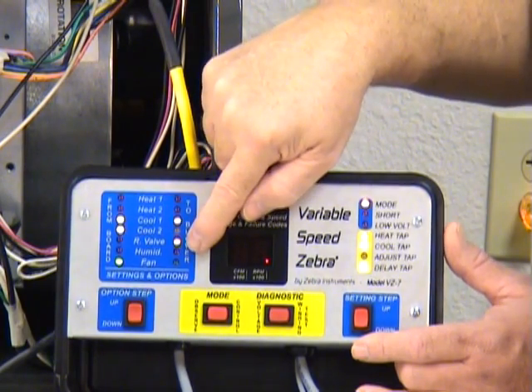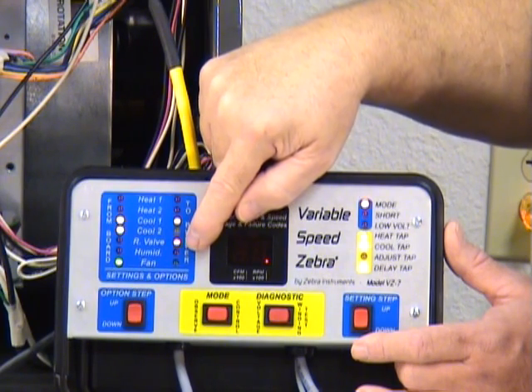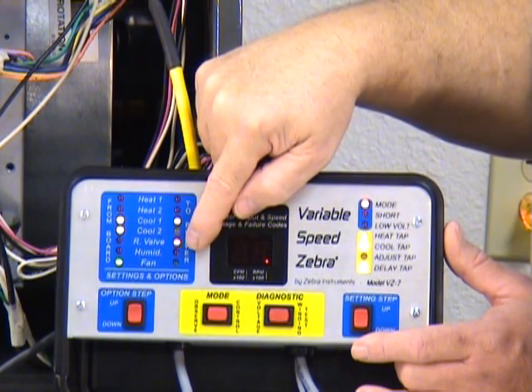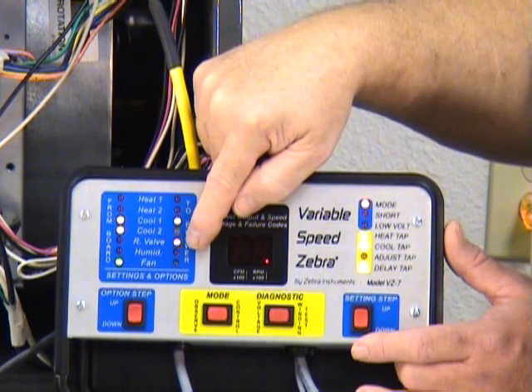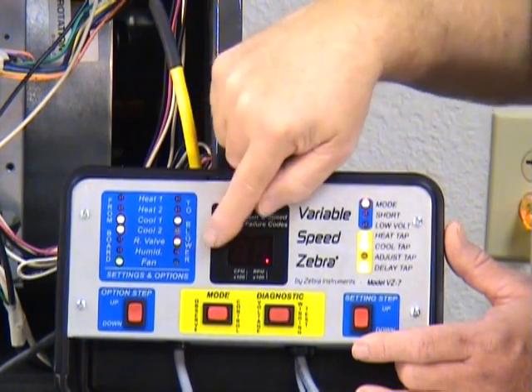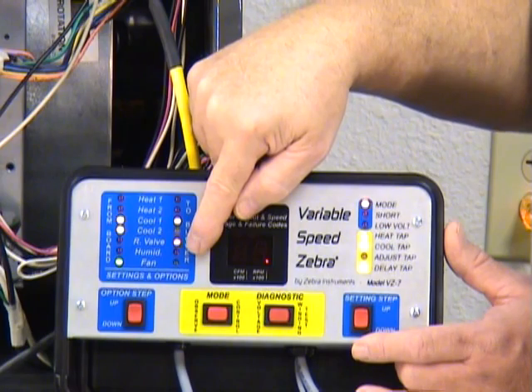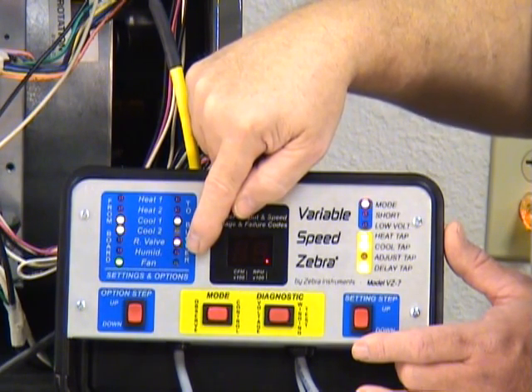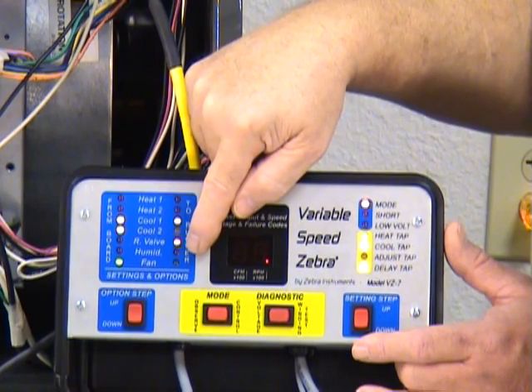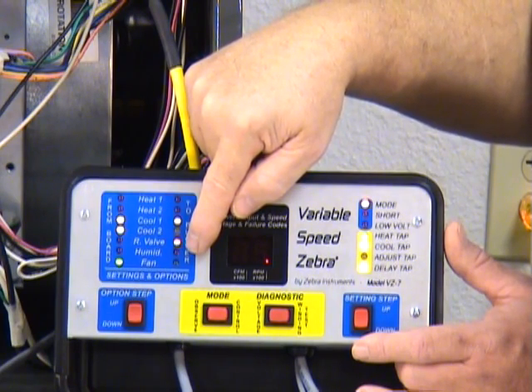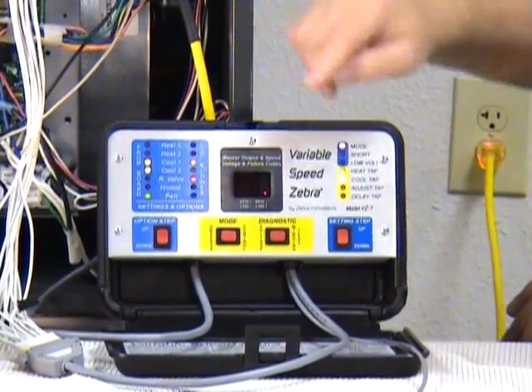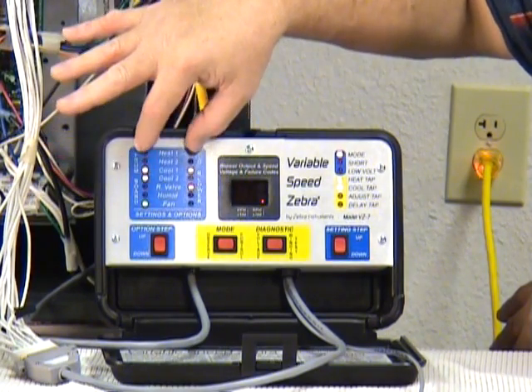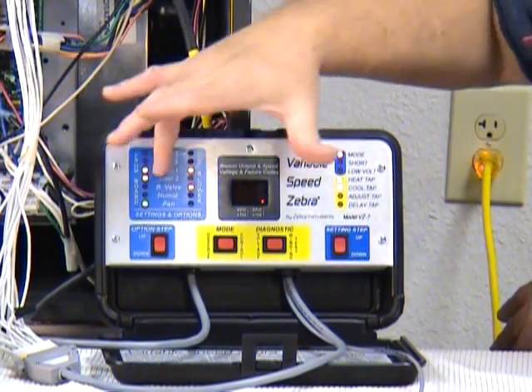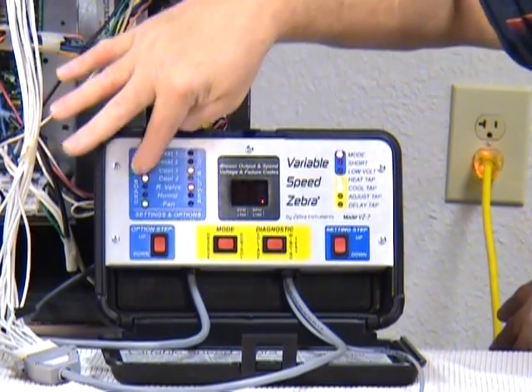The humidity line or humidistat line is when you have a call to reduce the airflow over the coil to increase your temperature difference so that you can remove more moisture from the air. When that line is active, typically your motor will slow down a few percent so that that TD increases, and the rate of condensation removal, of course, will increase too. So we've talked about which mode you're in, observe or control. Observe passes along those signals. Control splits those signals so that whatever is coming from the board stays there, but it doesn't get to the motor.